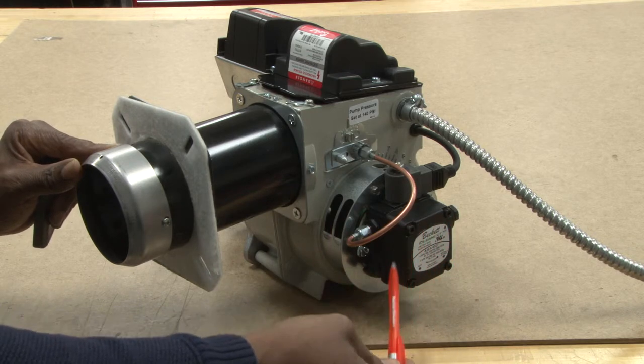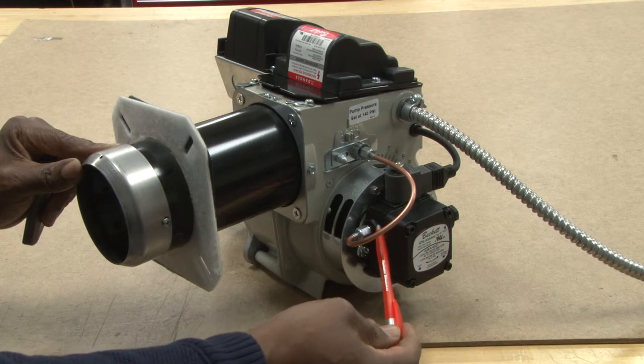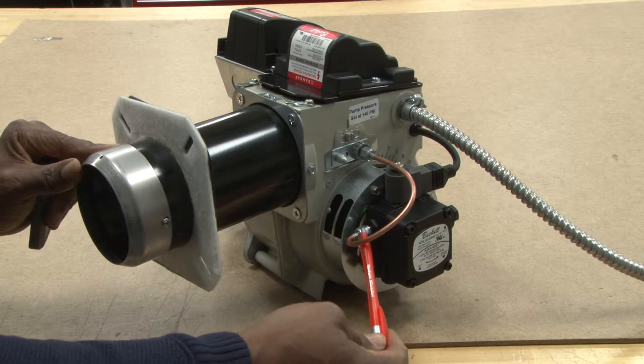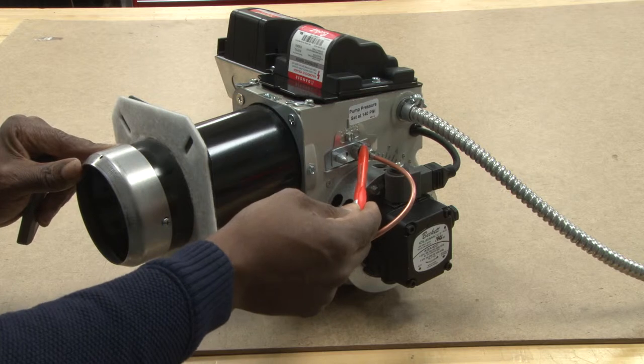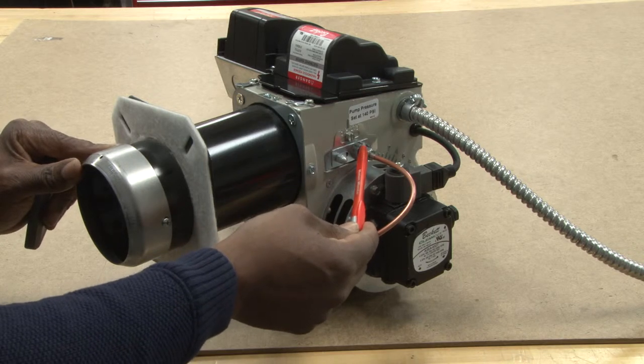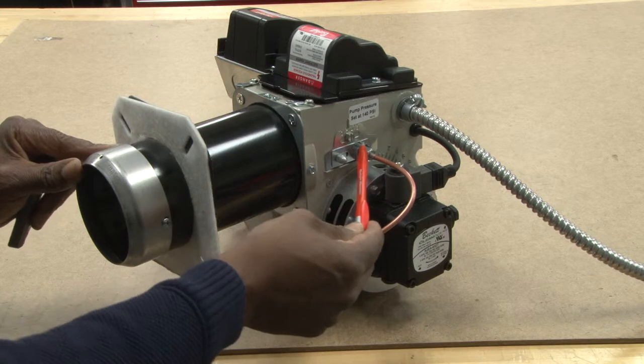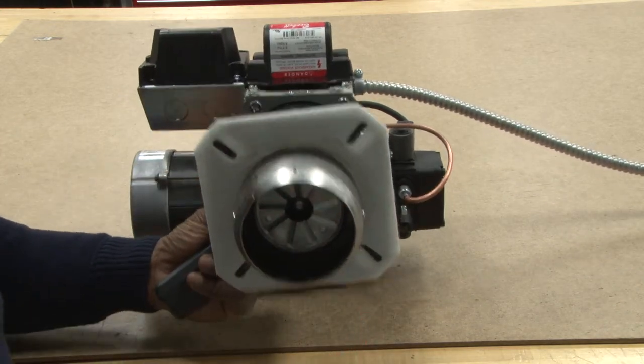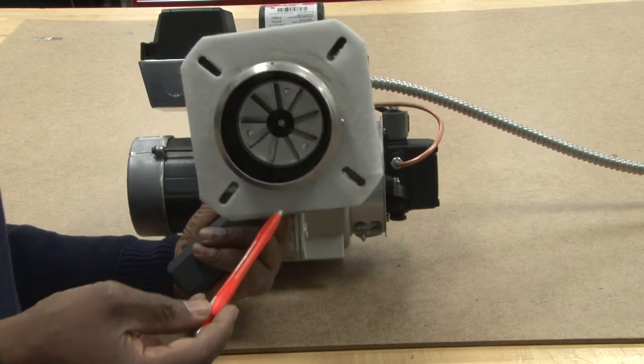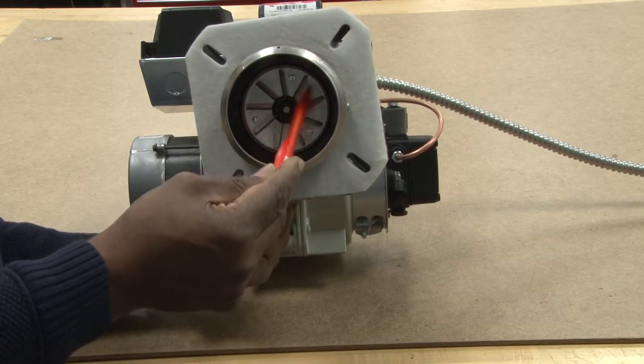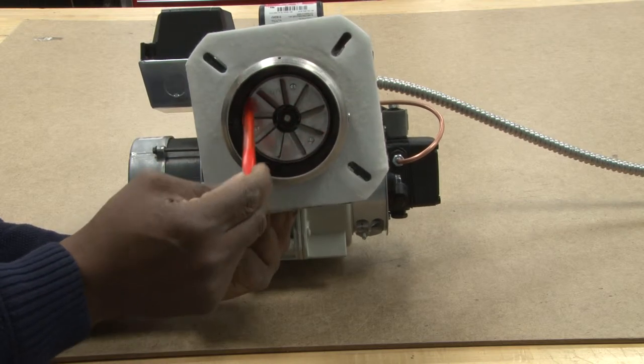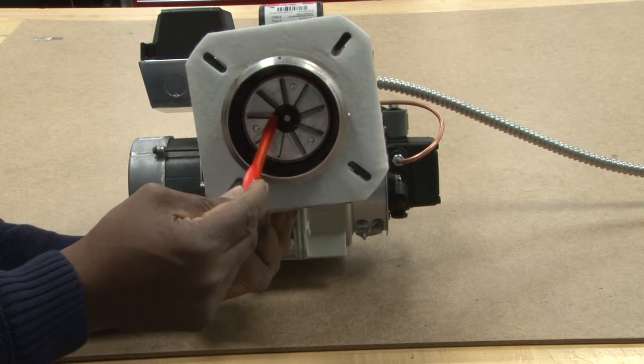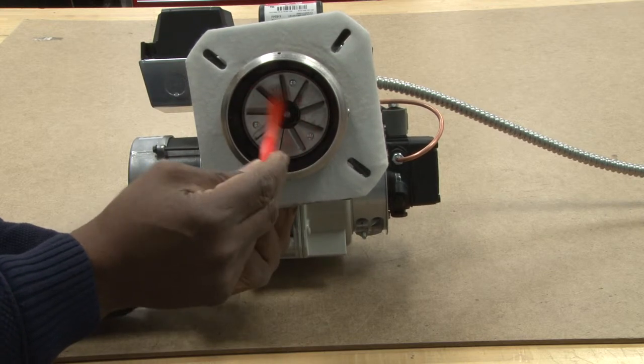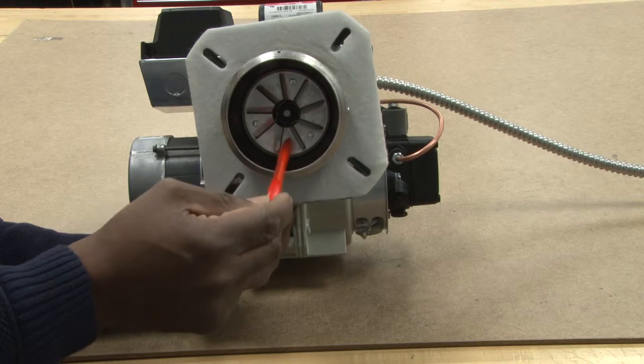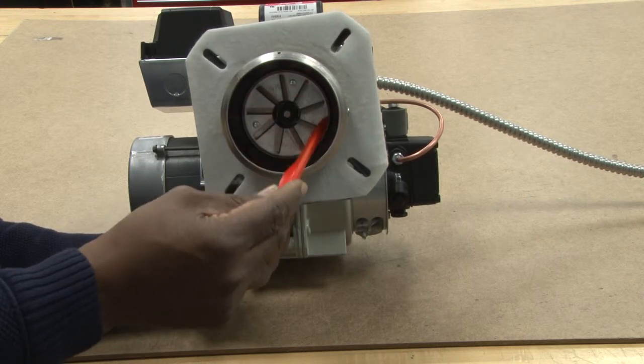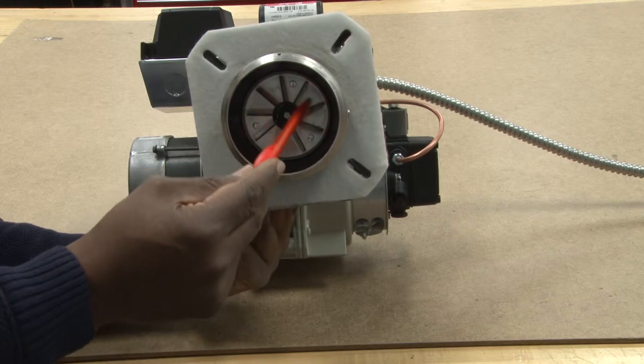You can see the pump a little bit better now. Attached to the pump is the discharge tube, or the discharge line, going to the inside of the burner where the nozzle and the igniter are located. Let's see if you can see the inside of the burner. This is a retention head. It's almost like a turbine, but it's a retention head which is designed to swirl air with the oil, which is in a mist, to create a certain type of flame pattern.